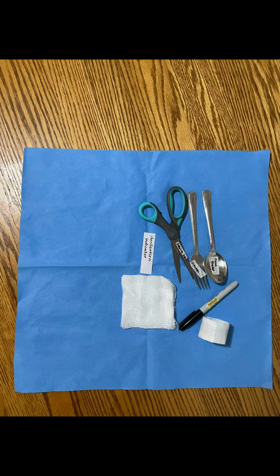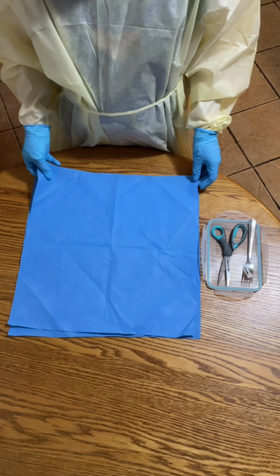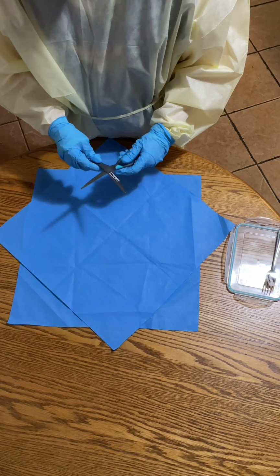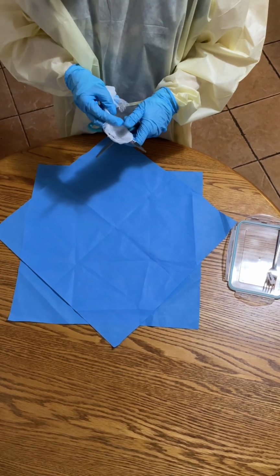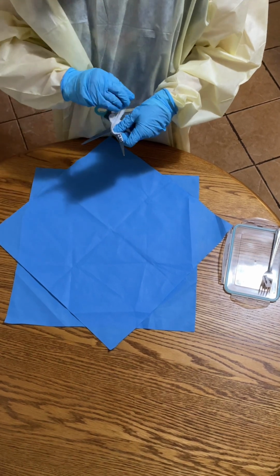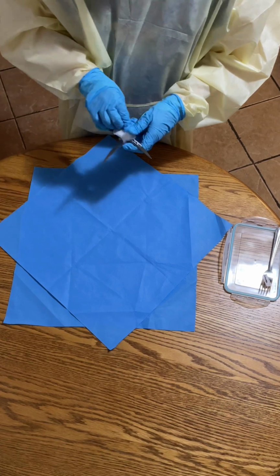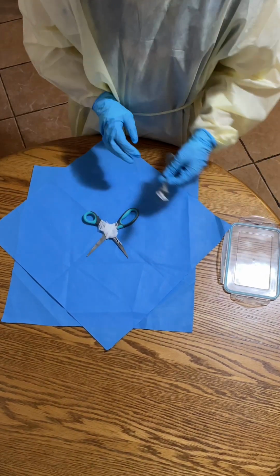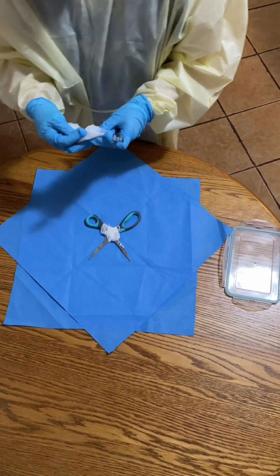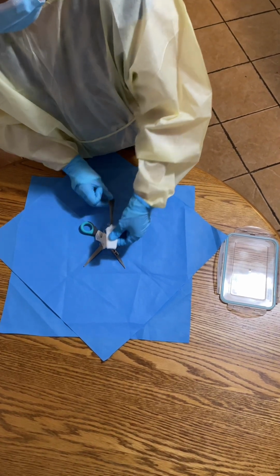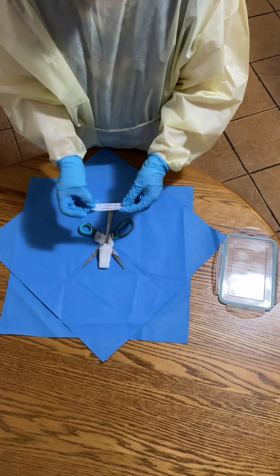In wrapping instruments, we need permeable autoclave wrapping material, autoclave wrapping tape, felt tip, sanitized hemostat or your instruments, cotton ball, and sterilization indicator. First, we need to wash our hands and assemble all necessary items. Ensure that items have been sanitized before wrapping for the autoclave process. Check items for flaws and make sure they function properly. And then place a cotton ball between any hinge instruments and keep all ratchets open during the sterilization process. Put a sterilization indicator in which the instruments can be wrapped. Wrap the tip of the sharp instruments with gauze to avoid puncture of the wrapping materials that causes contamination.